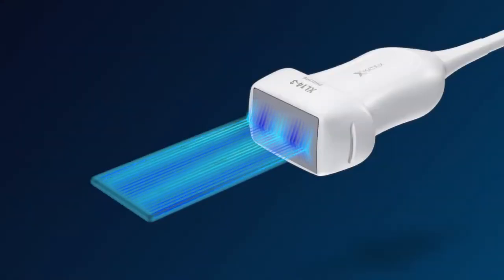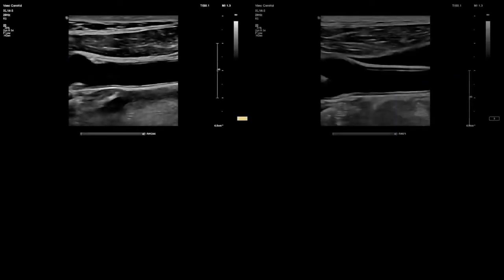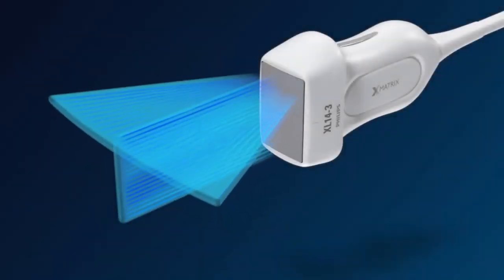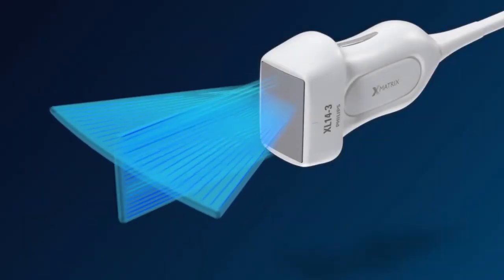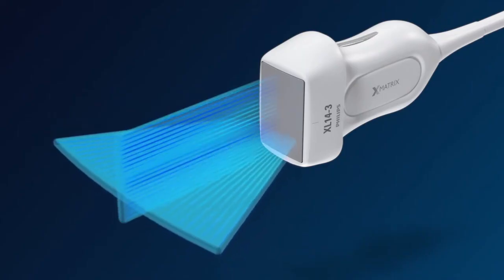Let's begin with straight linear array probes. The straight linear array probe is designed for superficial imaging. The crystals are aligned in a linear fashion within a flat head and produce sound waves in a straight line. The image produced is rectangular in shape. The probe has higher frequencies, 5 to 13 megahertz, which provides better resolution and less penetration. Therefore, this probe is ideal for imaging superficial structures and in ultrasound-guided procedures.